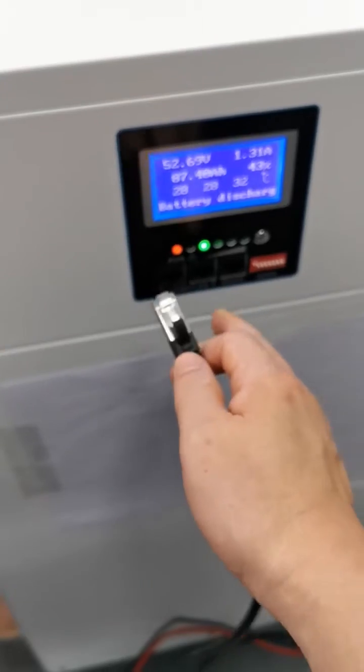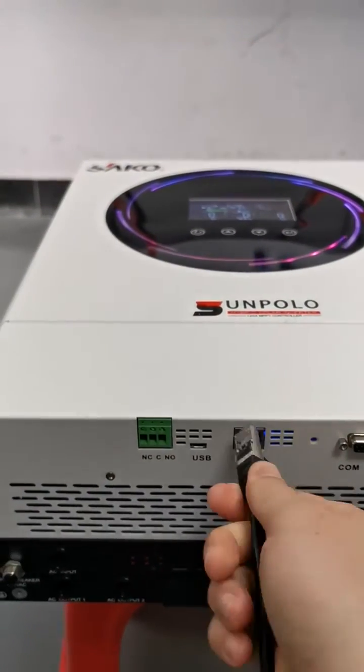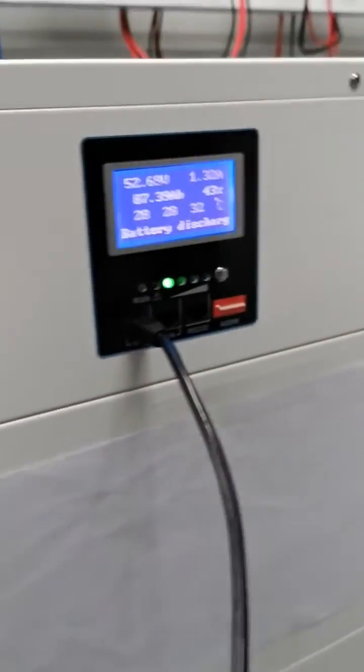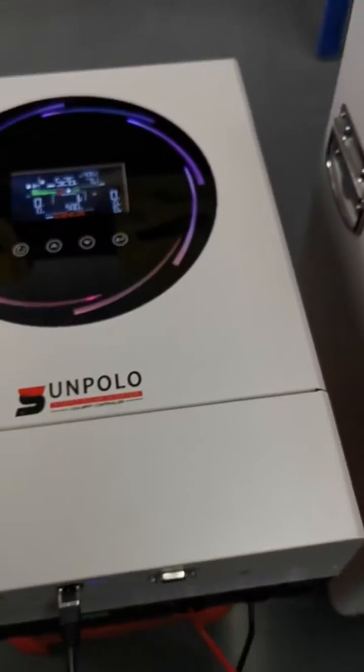We need to insert the RS485 cable into the battery port on this side, and insert the other end into the inverter BMS port. Pay attention: if you are linking with one battery, you need DIP switch number one turned on. Then check the screen.